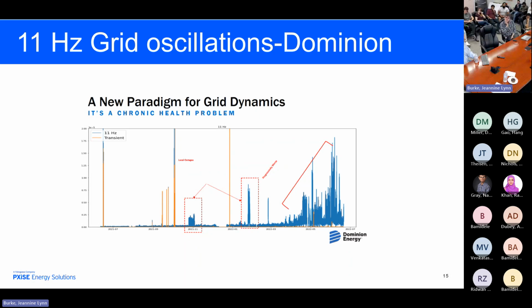I had only seen the oscillations that Manny typically shows us, under 1 hertz oscillations in a large power grid. This is 11 hertz. How are we going to control 11 hertz? According to Nyquist, we better control at 22 hertz. Why not just go all the way to 60 control and let's control at 60 hertz? And now we can dampen these frequencies.